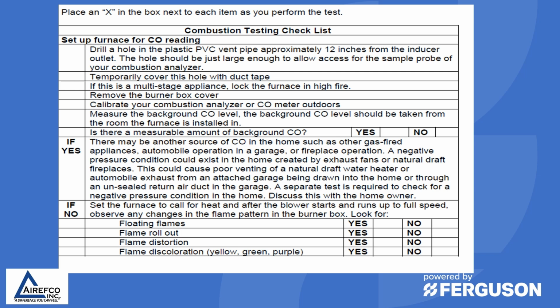So when is it necessary to open up a gas furnace to check out the secondary heat exchanger? Normal furnace operation should be well below 100 parts per million. Any reading over 100 parts per million tells the tech that it is time to open up the furnace and see what is going on in the secondary heat exchanger.